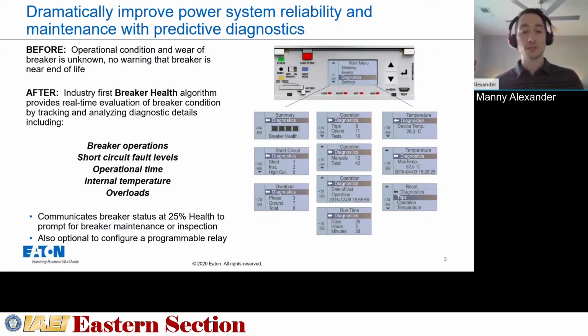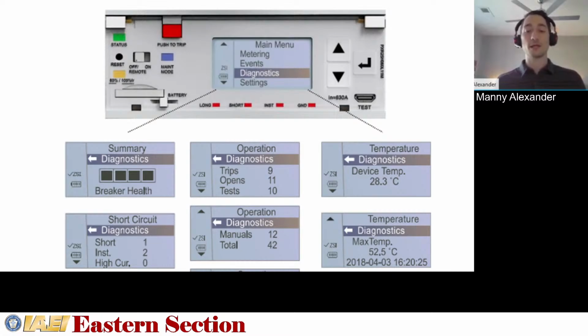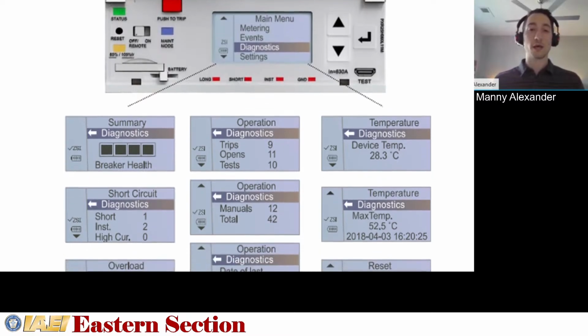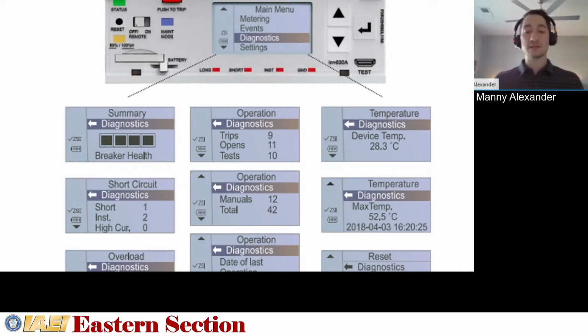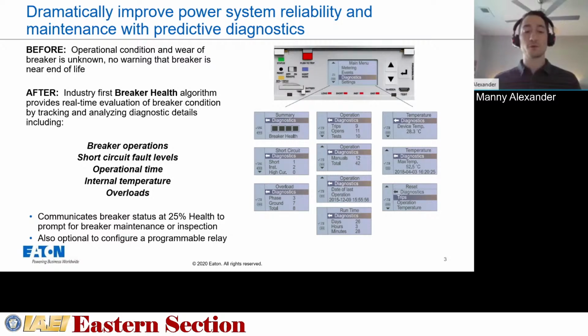So, these PXR trip units incorporate all of these metrics into a proprietary algorithm that we call breaker health. And it gives that real-time health percentage of the breaker. If the breaker sees standard use, the breaker health will go down slowly over time. If the breaker sees significant fault hits or maybe excessive physical operation, the breaker health will degrade faster. So that raw data is collected by the trip unit. It can be viewed as individual metrics or aggregated into that total health measurement up to 100%. With this information, scheduled maintenance can be performed based on the system health, or a breaker that is nearing end of life can be replaced to avoid that unplanned downtime.